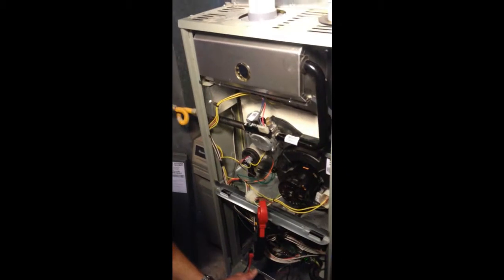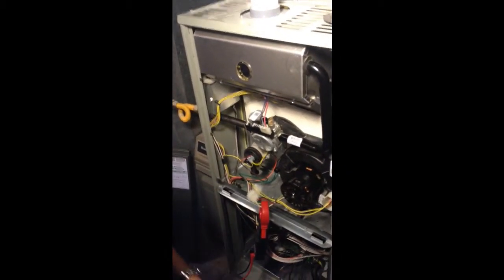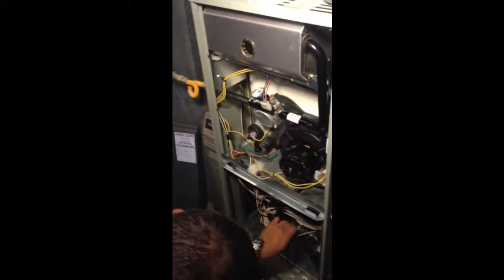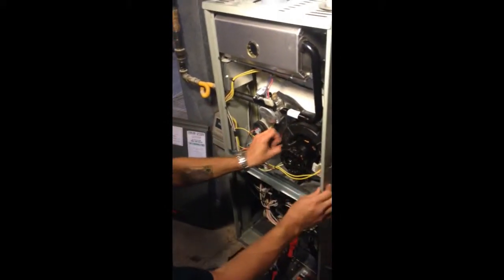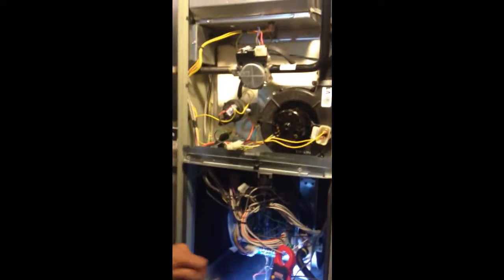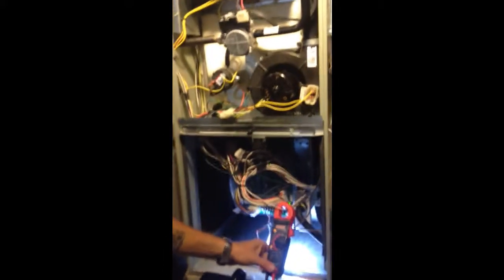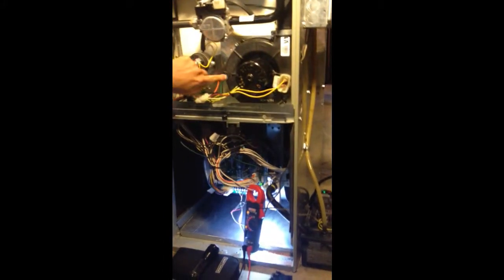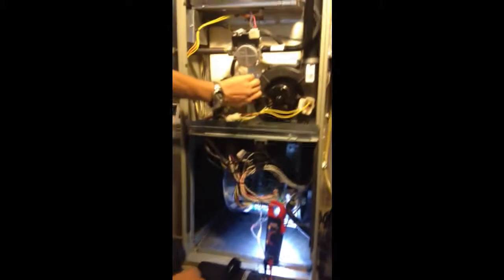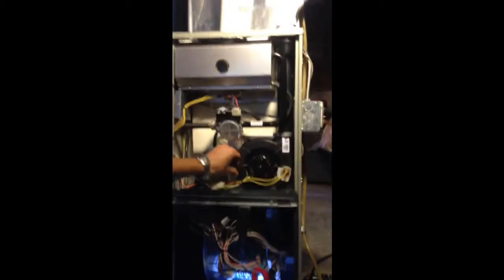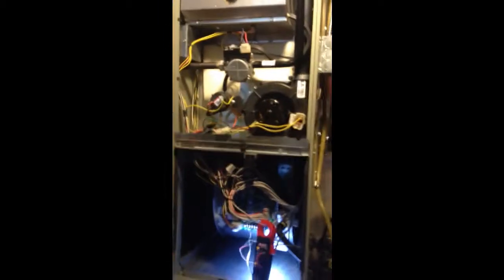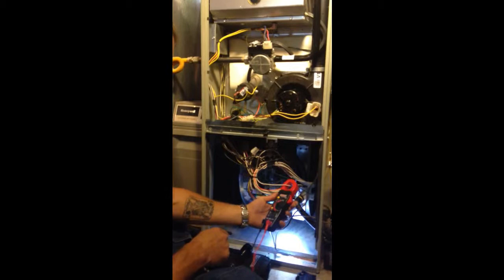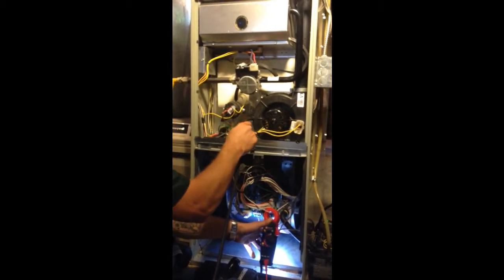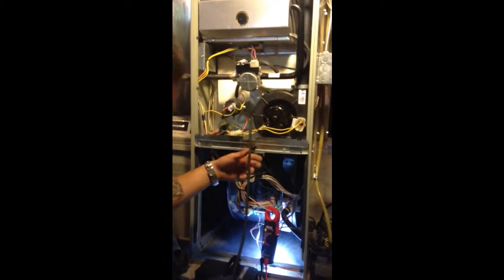And our fire turns on, jumps over, the flame rod will sense that there's fire, and then it'll tell the circuit board, go ahead and turn on the blower. So, while we're waiting, kind of ramp up. And that is high fire, and that's when we can do our carbon monoxide test. Right here, it's really convenient. These inducers have a little plug, so you don't have to drill a hole like someone in the past has done up there. You can just pop this out. Wait for that to go into high fire. Going into high fire. At the same time, I'm looking at my amperage reading from the blower motor. So I'll stick this in here, and I'll hit run on here.